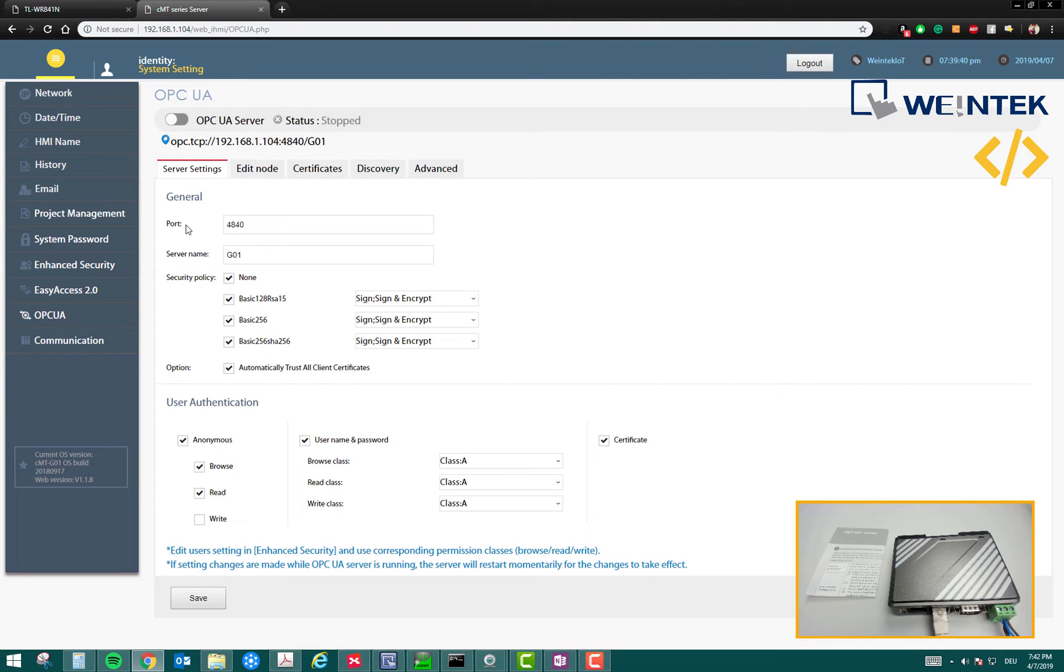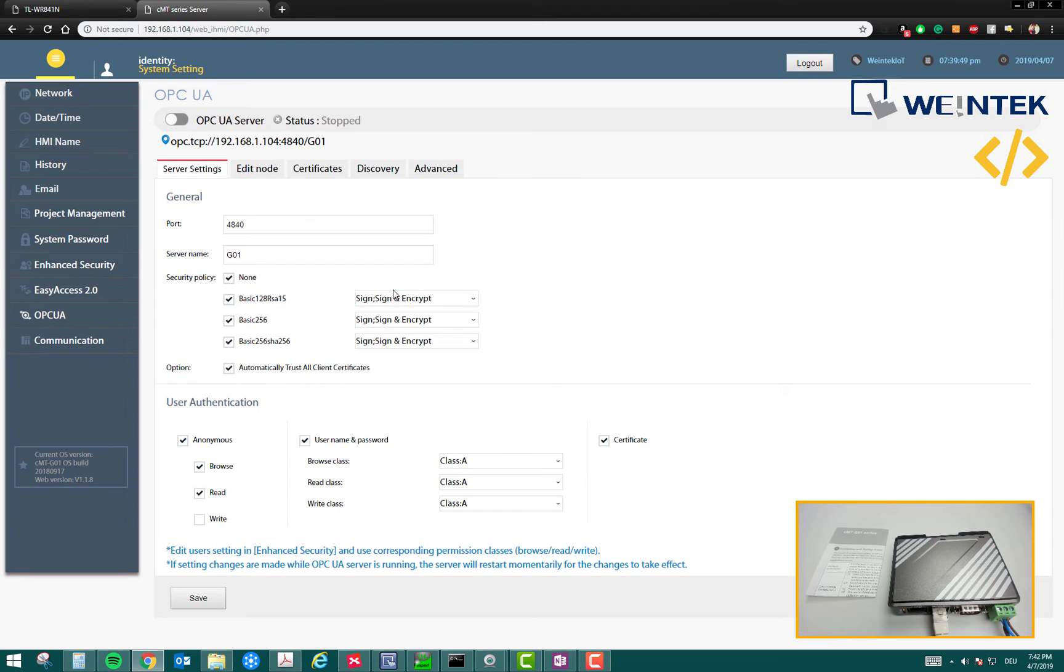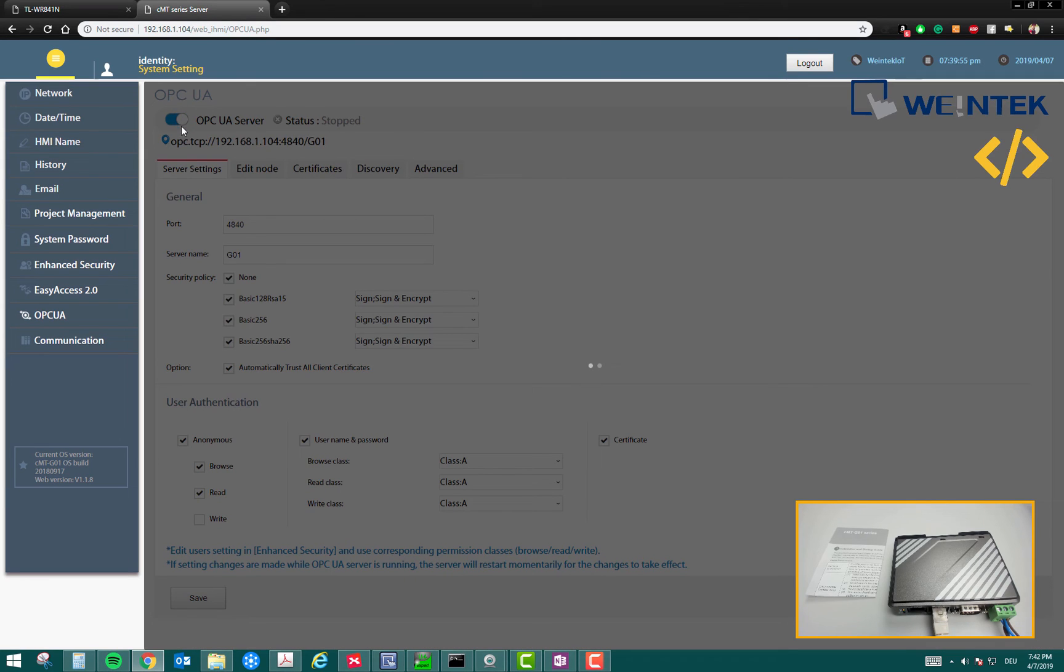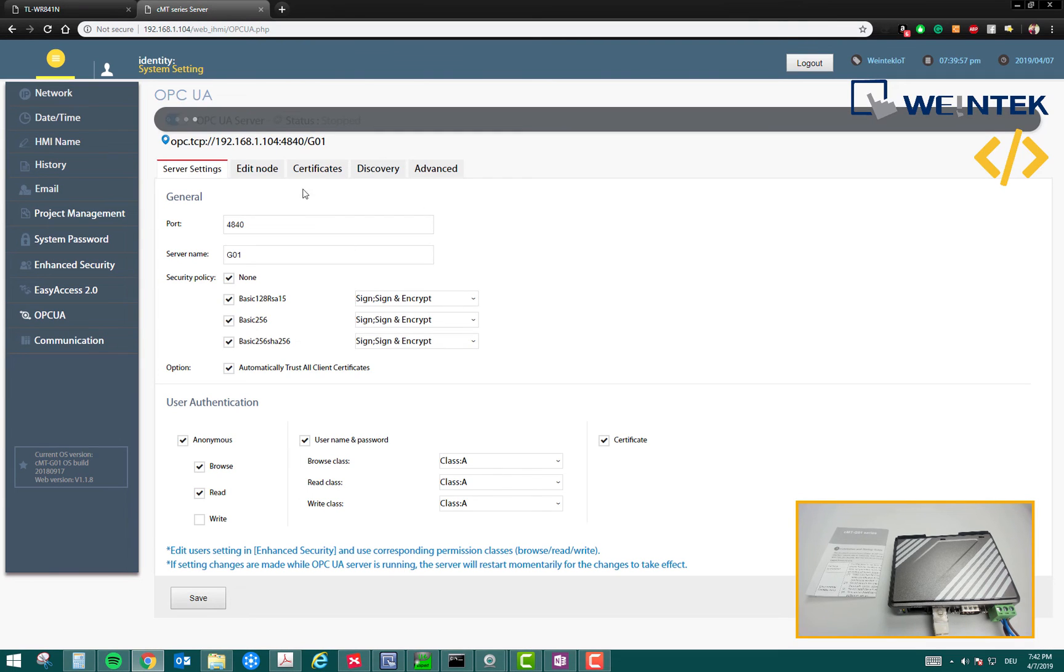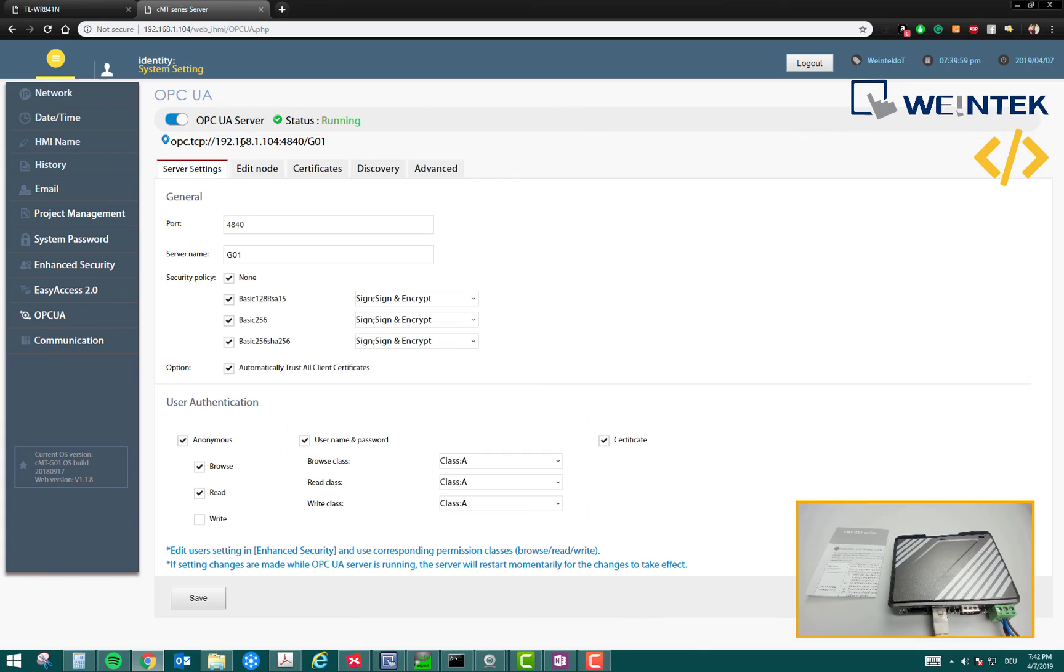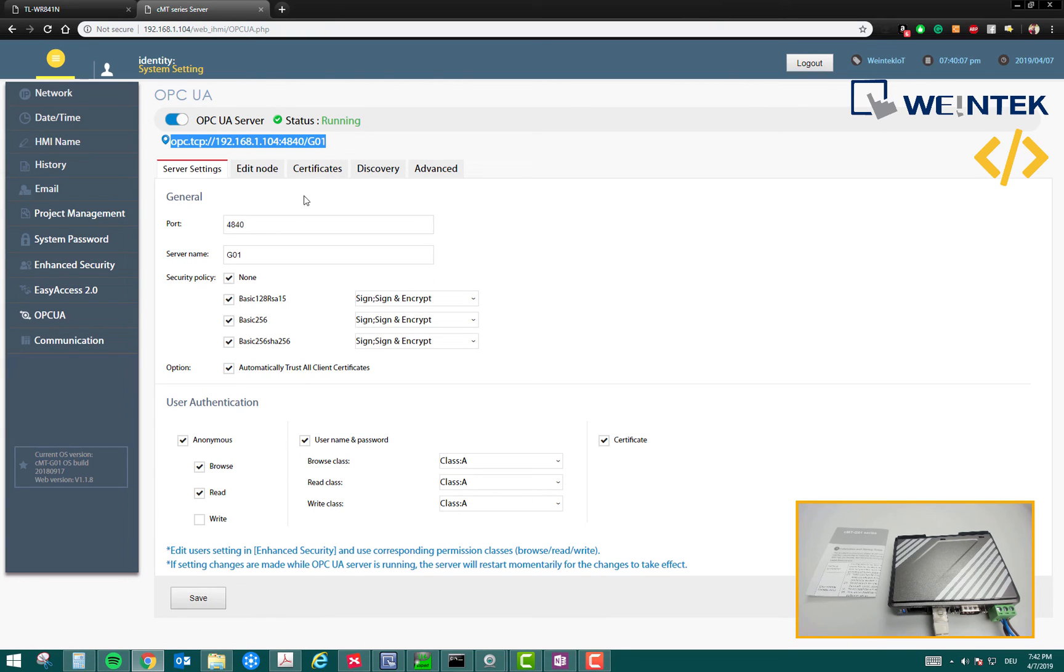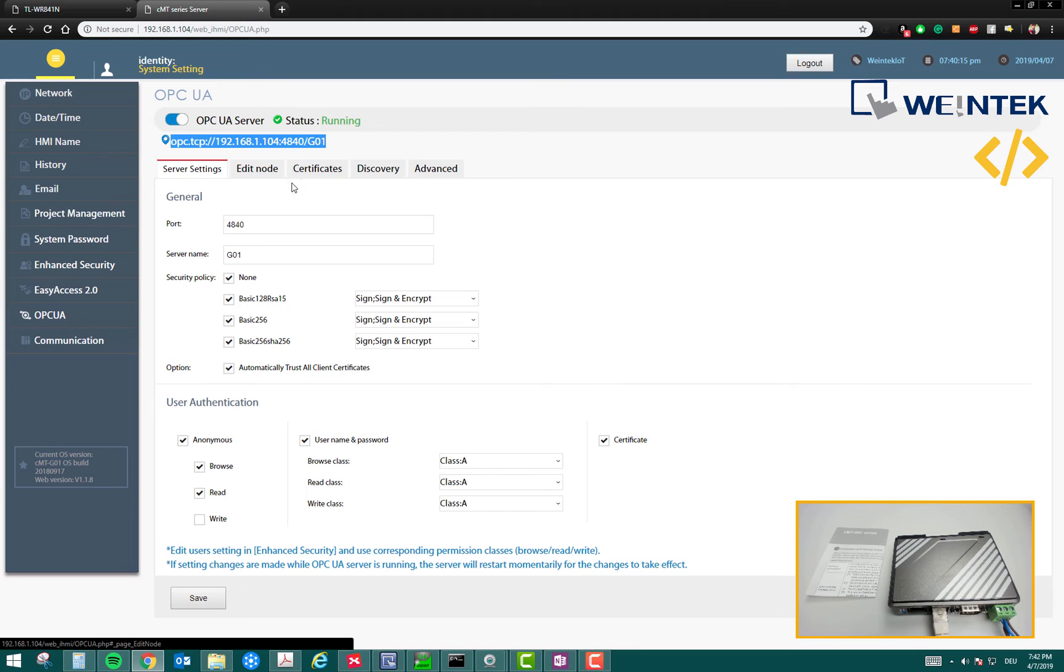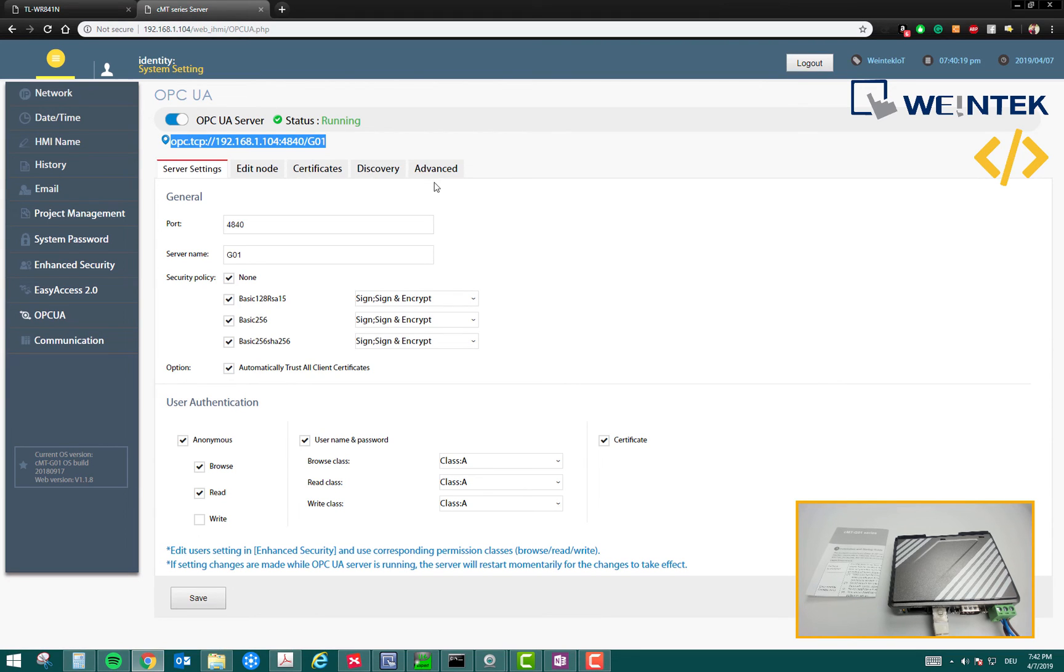I'll be using a Delta PLC and a Siemens PLC to read the information. This OPC UA server can further send this information to whichever client will request it. Currently you can see that the status is stopped. You can also enable it. Once you enable the OPC UA server, this is the OPC UA endpoint. This is the main link or the information you need to access to the server. We will come back to this when we are going to set up a device for this OPC UA. You can edit the nodes, define the certificates, and discover your device and some advanced features.